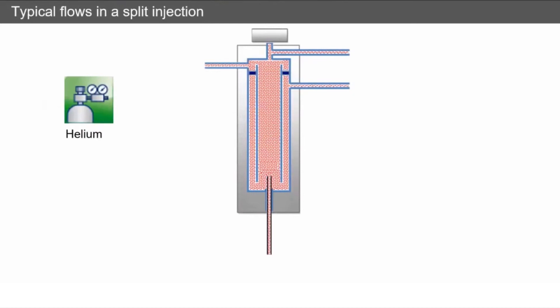So typical flows in a split injection: we've got our carrier gas inlet which would be say 56 milliliters per minute, septum purge which is 5 milliliters per minute, which is just like I said, getting rid of things like septum bleed, etc. But coming out of our split vent we've got 50 milliliters per minute.